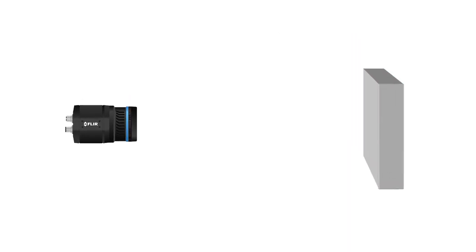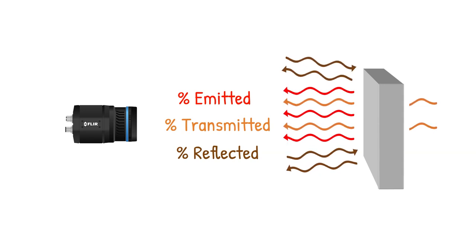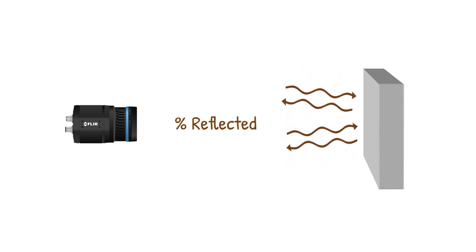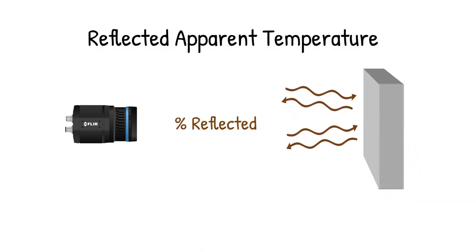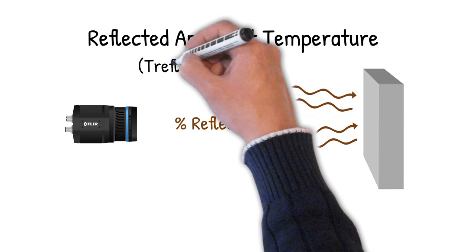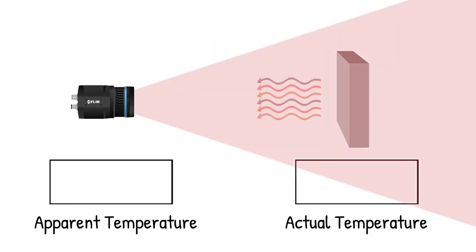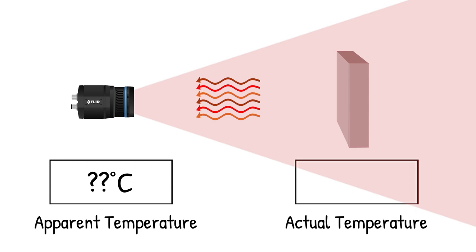As such, the total radiation reaching the infrared camera could be a combination of emitted, transmitted, and reflected radiation. The temperature associated with the reflected radiation is known as the reflected apparent temperature. It is also known as T-reflected or T-background. The infrared camera sees the total radiation from the target of interest and cannot differentiate between the various radiation sources.